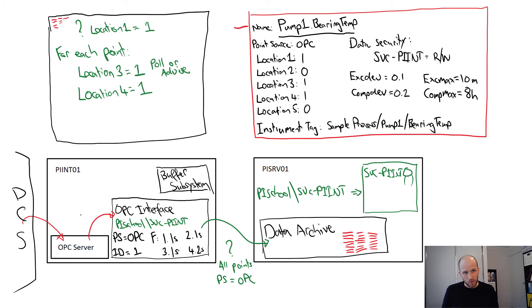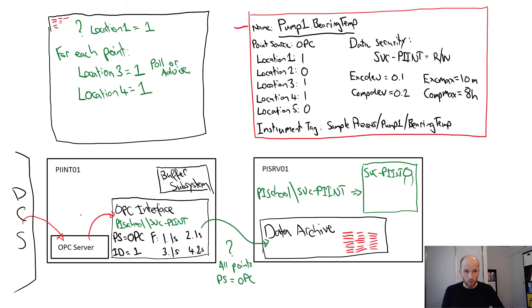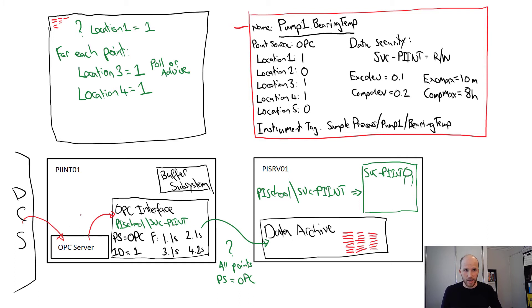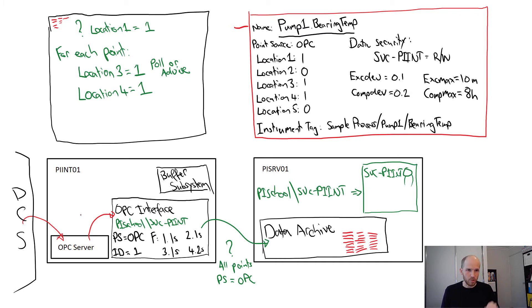If your server has limitations on how many tags can be loaded in a single OPC group, the server will call these groups, you can split up your tags into different groups by assigning them to different scan classes. This is why we've got three scan classes, all of them being one. So you can split up your tags there, and it'll make them assigned to different groups on the server.